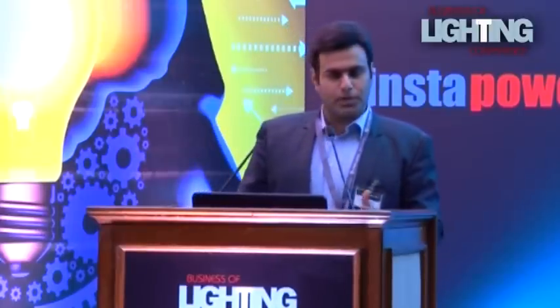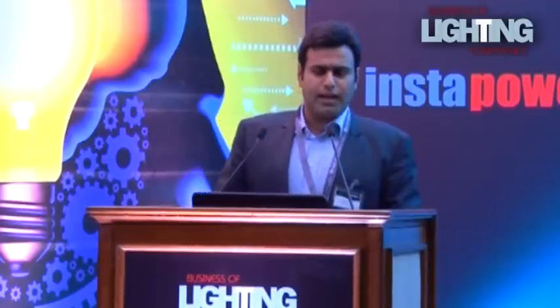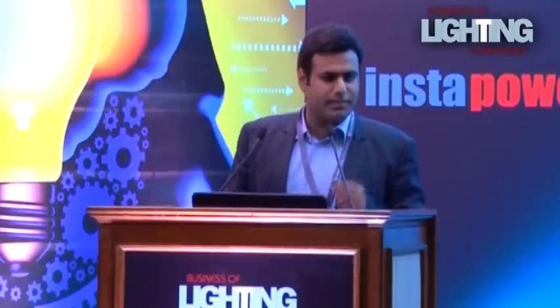The third dimension of lighting, which is called the biological effect, is what we talk about. It affects my efficiency at work. There's a study at the University of Washington which highlights that if I have appropriate uniformity in my building, if I have a UGR of around 22, if I have a daylight glare index of 90, my efficiency goes up by 20%. So if I talk about a huge corporate, say Infosys, which has lakhs of employees, and if I manage to increase the efficiency by 20-25%, I've done my energy recovery, I've done my payback. It gives me the sense of safety and the visual comfort sitting in the building.